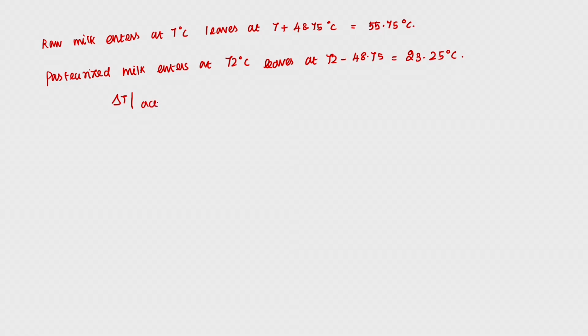Delta across the regeneration section: this is 72, this is 55.75, so 72 minus 55.75 degree centigrade, which is equivalent to 16.25 degree centigrade. So, del T across the exchanger is 16.25 degree centigrade.